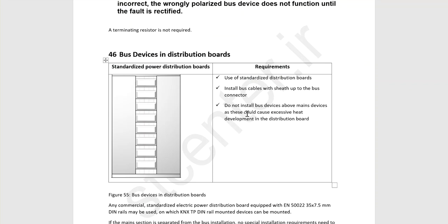Another concern is do not install bus devices above main devices, as these could cause excessive heat development in the distribution board. Maybe in your electrical cabinet you have a contactor, or power supply units, not KNX, other power supply units that generate heat. So you should put devices like the contactor and power supply units at the top level of the electrical cabinet, and put the KNX devices in the lower part. Even among KNX devices, if you use a dimmer or power supply, of course you should put it higher than other devices.